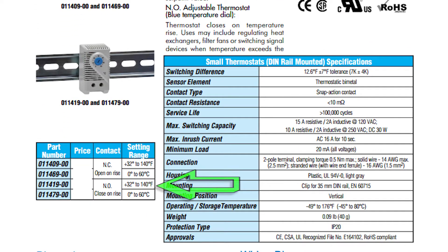The small thermostats we will cover in this video are listed on the screen. These four thermostats have adjustable temperature settings with ranges of 32 degrees Fahrenheit to 140 degrees Fahrenheit in normally open or normally closed configurations and versions in 0 degrees Celsius to 60 degrees Celsius in normally open or normally closed configurations.